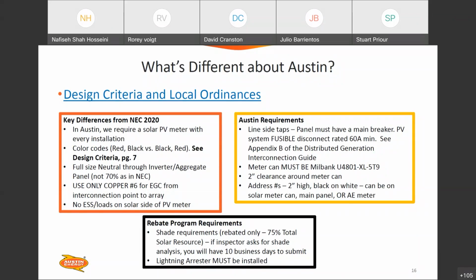Please leave 2-inch clearance around all sides of the meter can, for future serviceability. Equipment walls get tight sometimes, but keep that tape measure on you—2 inches on all sides of either meter can, billing or solar.